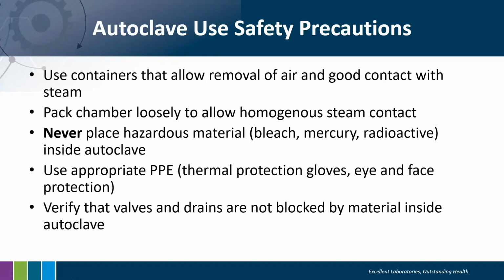We talked about the inside of the autoclave, and how to have whatever you want to autoclave placed inside in a manner that allows for steam contact, but it's also important that when you pack the material to be autoclaved, you take that into consideration. For instance, that autoclave bag needs to have a standardized opening, to allow steam to get in contact with the waste inside. Some folks will close the bag really tight, and that won't allow steam to get in contact with the content inside the bag. So that's not a good practice. And of course, as I mentioned before, never, ever place hazardous materials such as bleach, mercury, or radioactive components inside the autoclave.